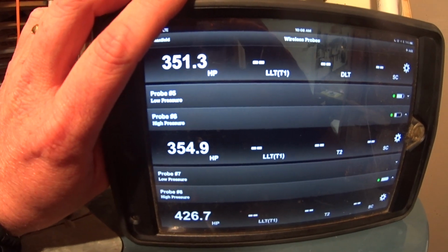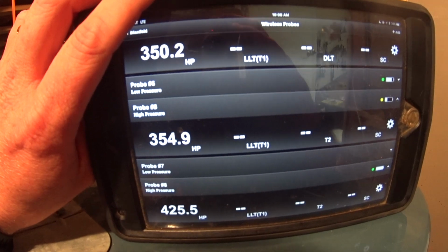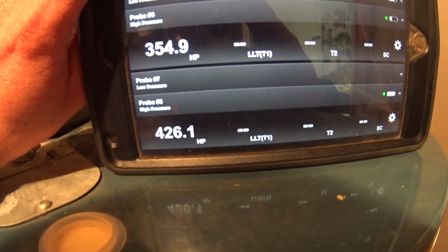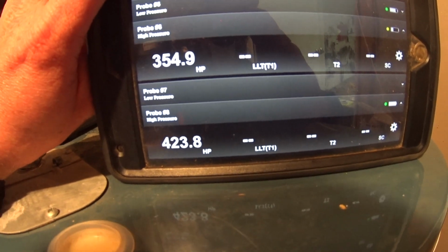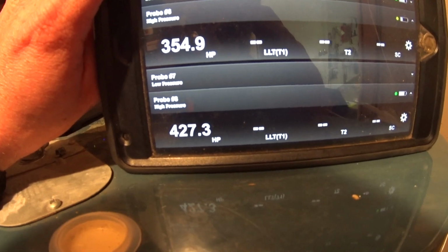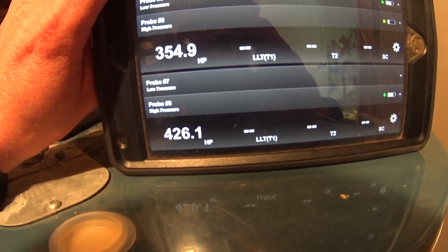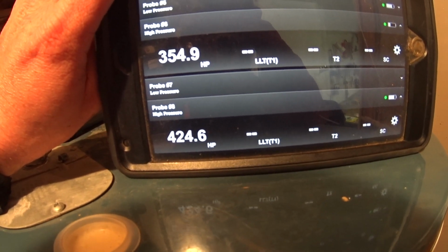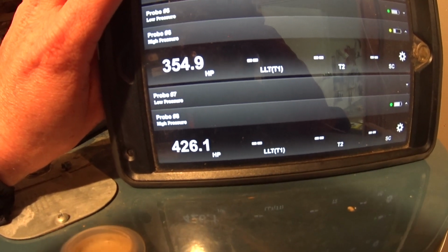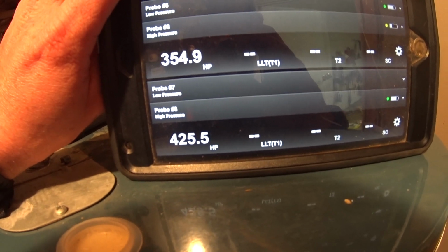Almost another 10 minutes later, the first 2 circuits are holding pressure nicely. I pushed the other one up to 425. That's what I ended up with after I pulled the hose off of the Schrader core, so that I wasn't adding another potential false leak. I'm not going to give that one a whole lot of time to confirm the leak, but I was unable to hear anything in the room. Too much ambient noise and other things going on to actually hear anything. It would have to be pretty loud.